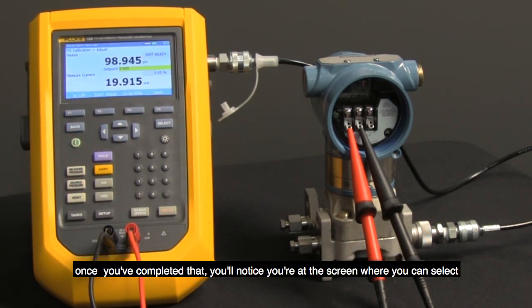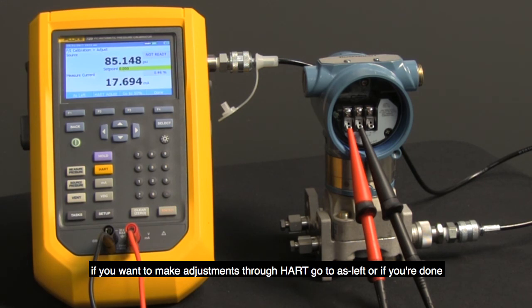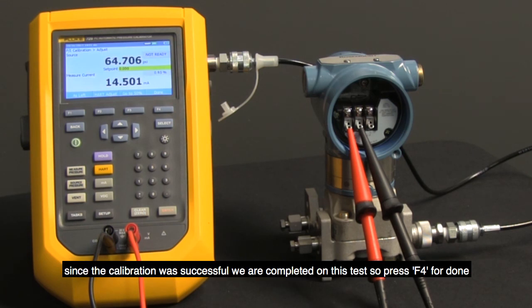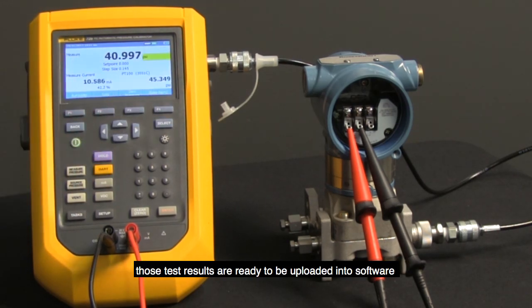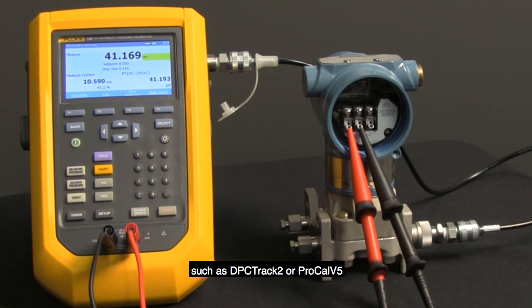Once you've completed that, you'll notice you're at the screen where you can select if you want to make adjustments through HART, go to as left, or if you're done. Since the calibration was successful, we are completed on this test. So we'll press F4 for done. And those test results are now ready to be uploaded into software such as DPC Track 2 or ProCal V5.